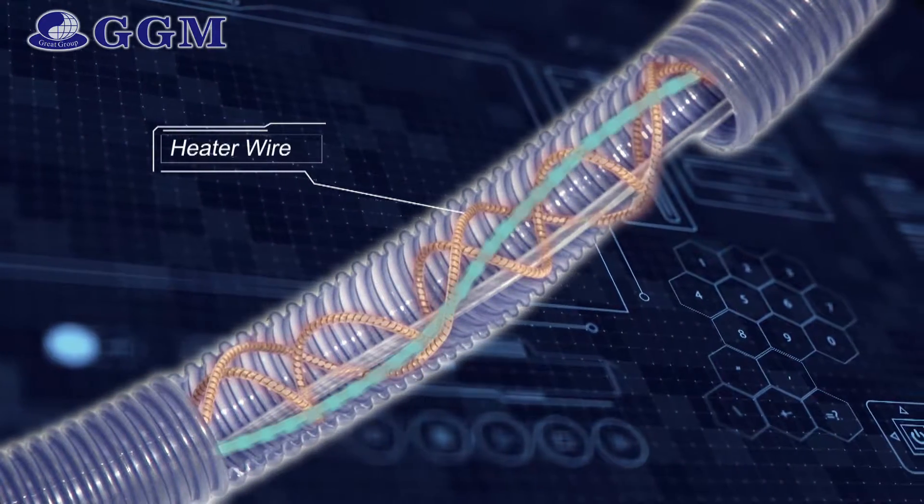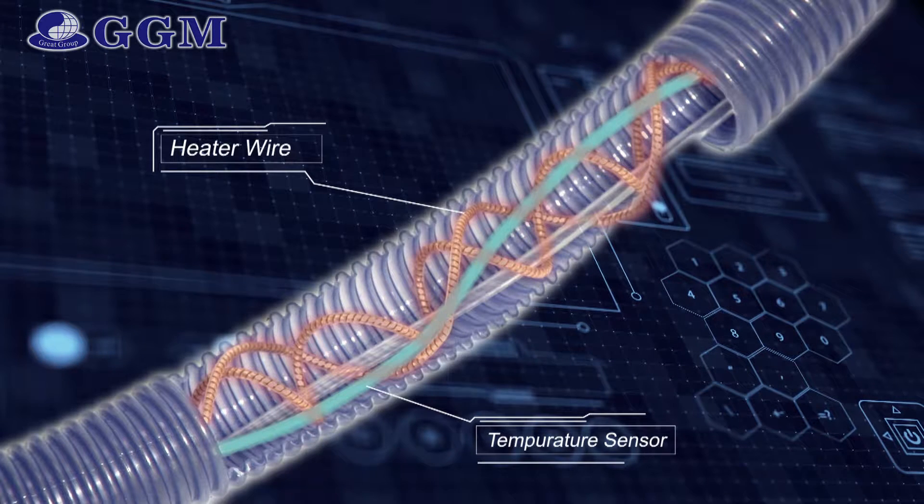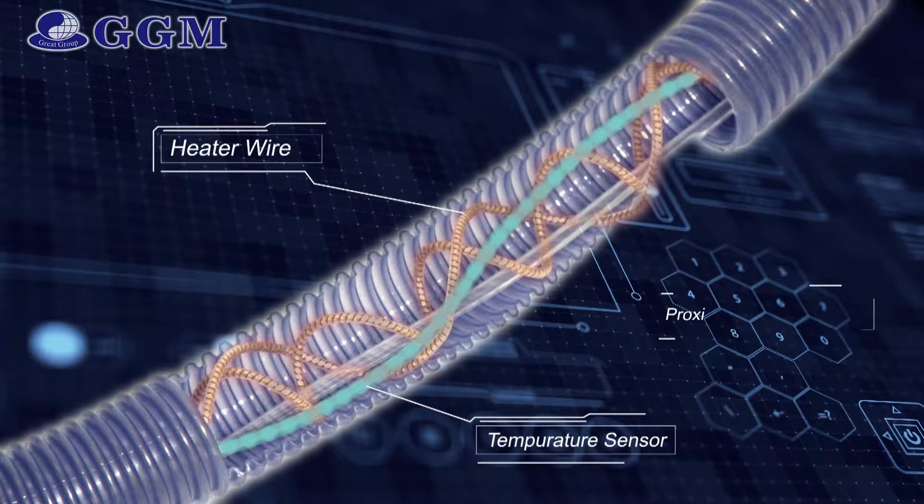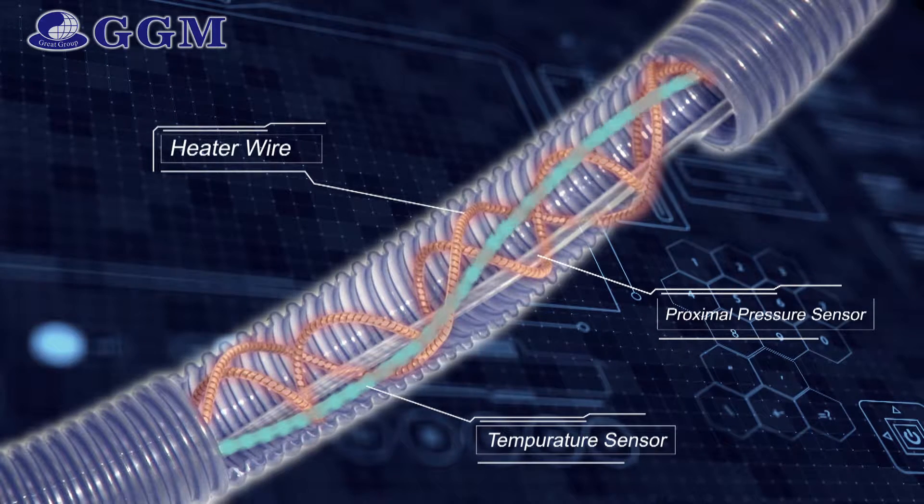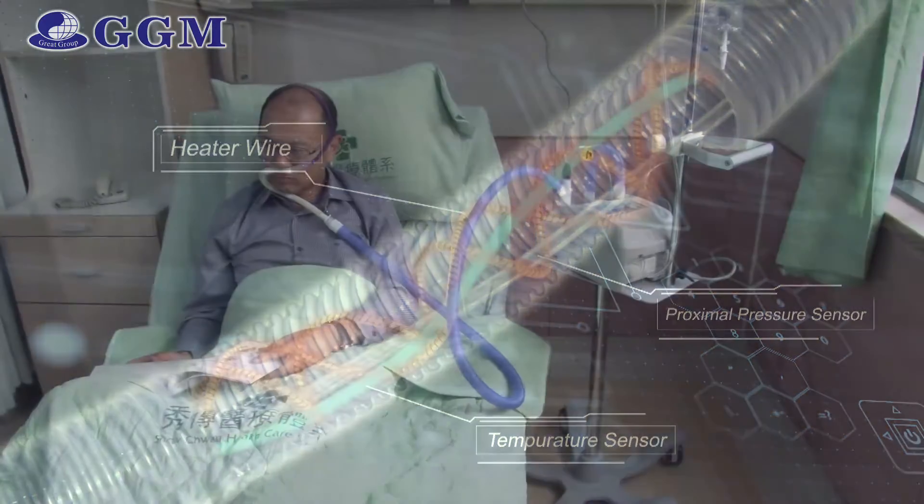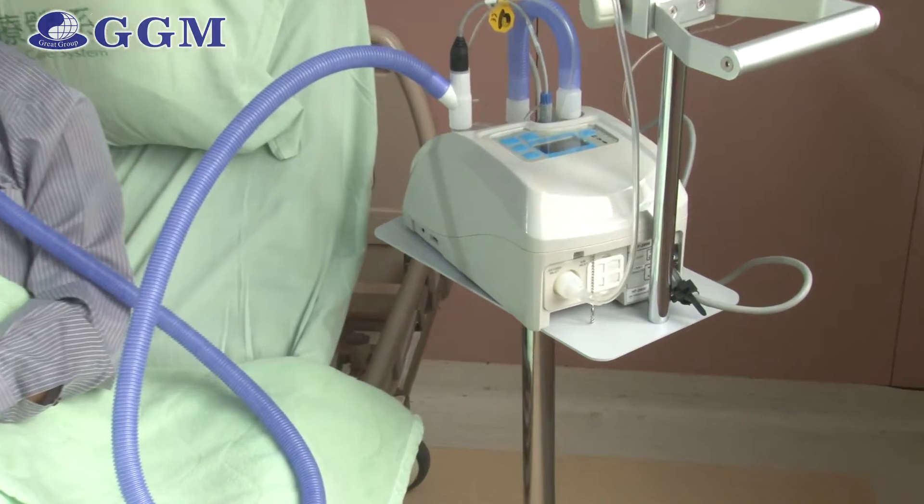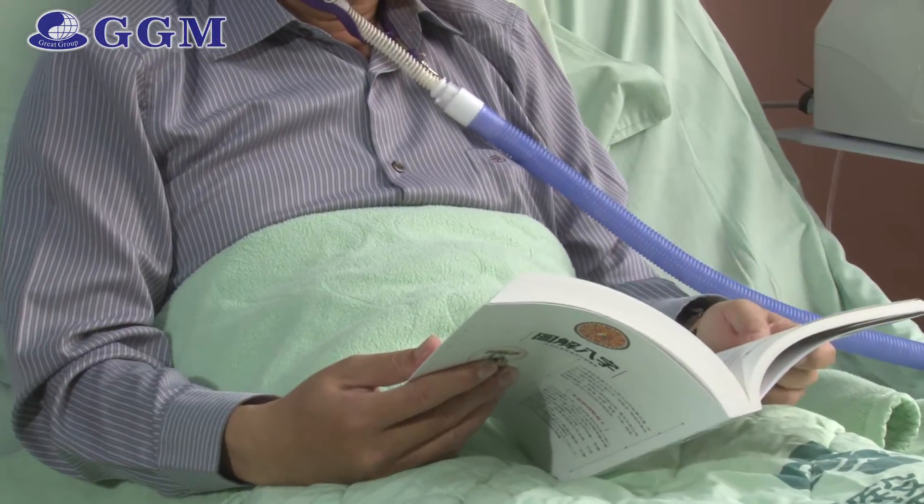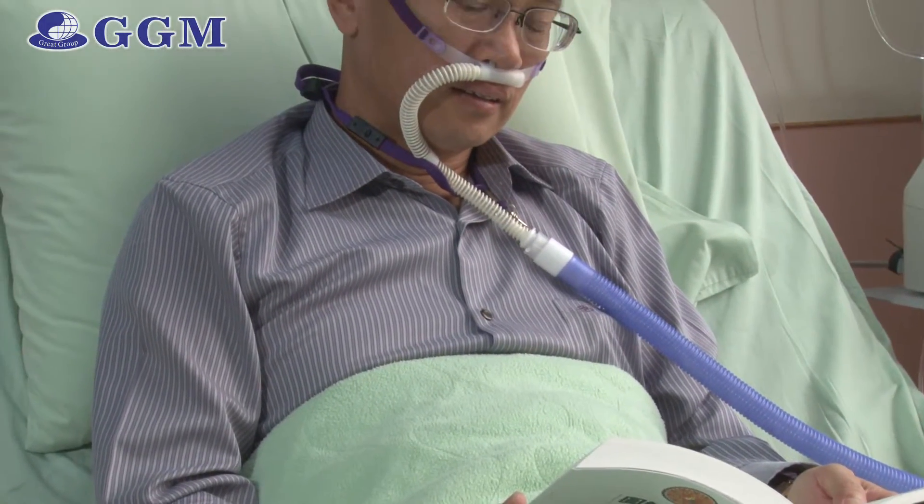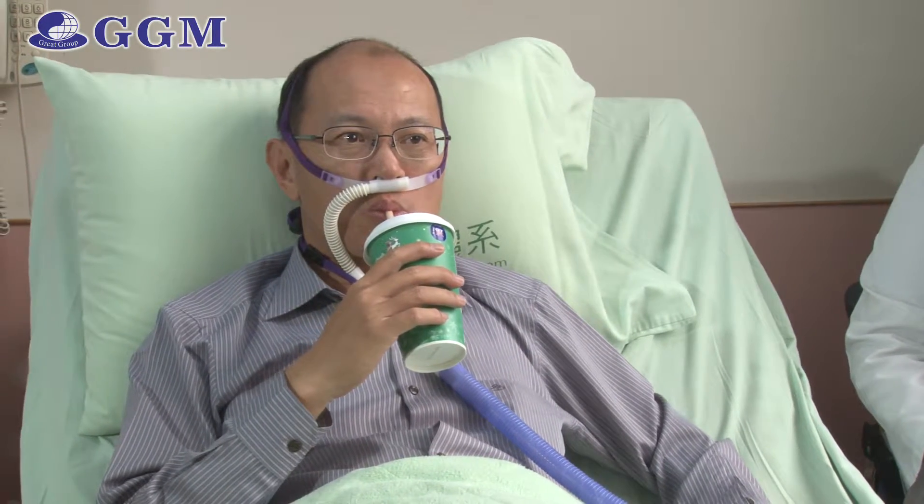A temperature probe and pressure line are also installed in the tube, enabling humidiflow to detect the airway temperature and proximal pressure. The humidiflow finally interacts with patients via our high-flow interface. It is ultimately comfortable, convenient and widely accepted by a full range of patients.